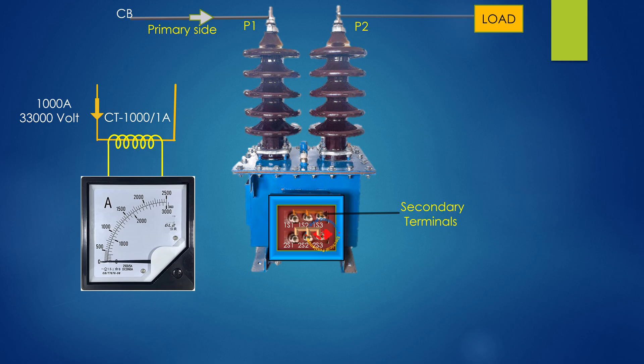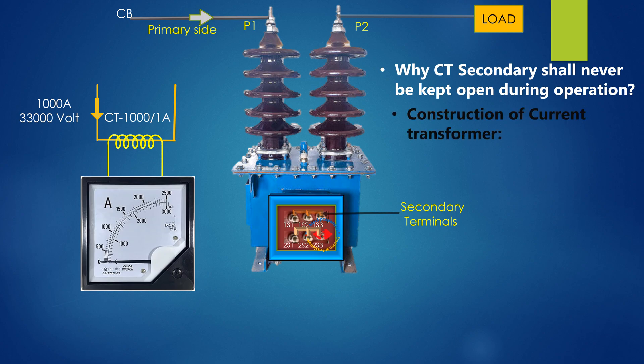Now we have the subject of discussion: why CT secondary shall never be kept open during operation. Open circuited CT can cause serious safety concerns like fire, electrocution and saturation of CT, thus protection failure. Therefore, we must ensure that CT secondary should always be kept short circuited. Let us now understand the CT construction and its working principle to know why the CT must not be open circuited.